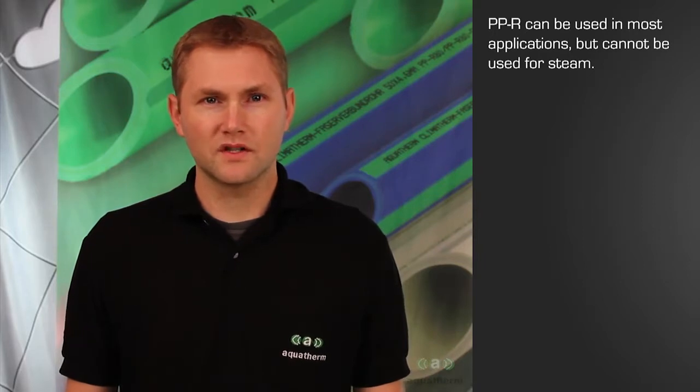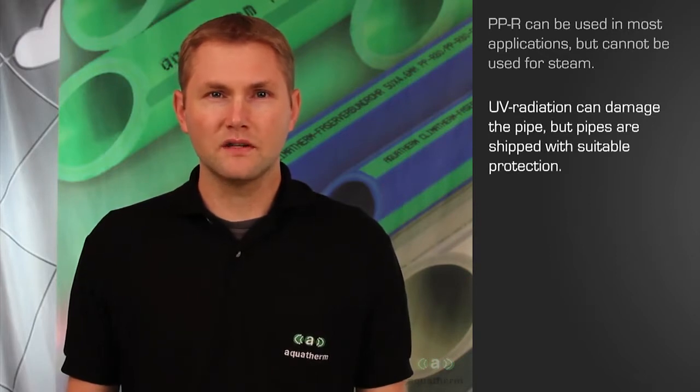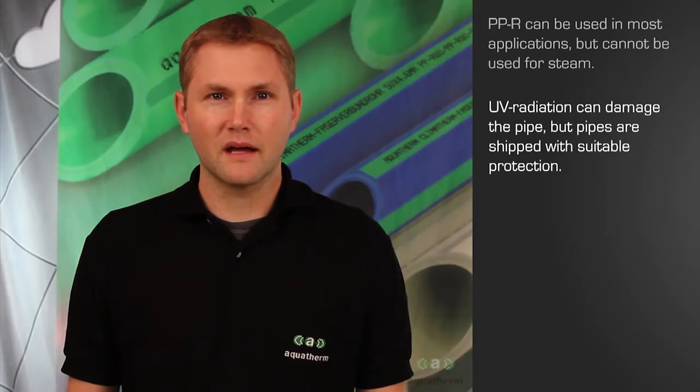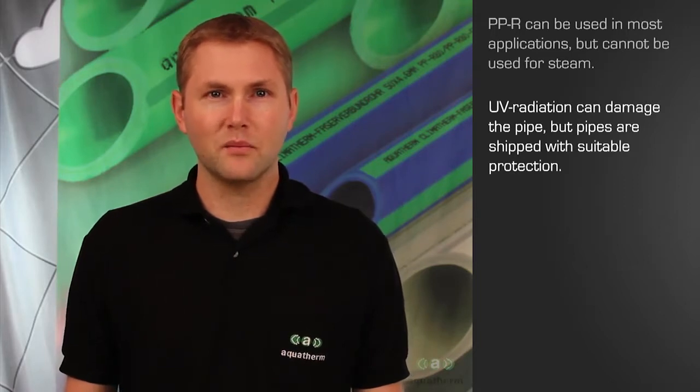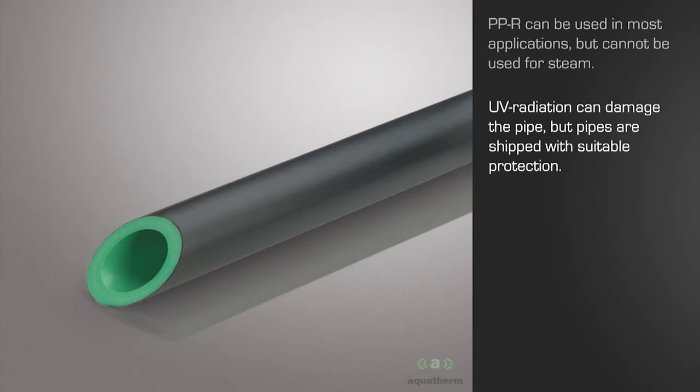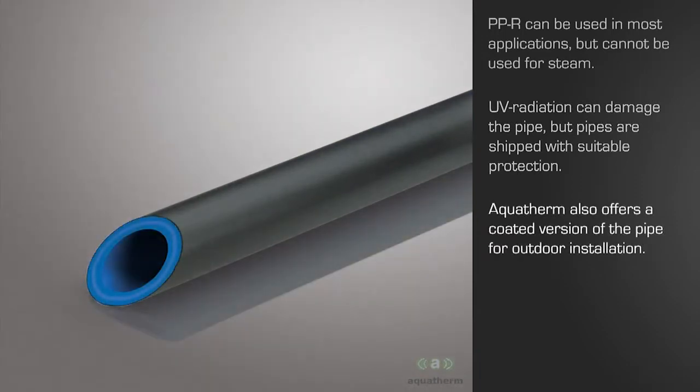The other issue is UV protection. If PPR is exposed to UV radiation for an extended period of time, the pipe can become discolored or even damaged. Accordingly, Aquatherm ships the pipe in UV protected bags that can be used indefinitely to protect the pipes before installation. Aquatherm also offers a UV protected version of the pipes for outdoor installations.